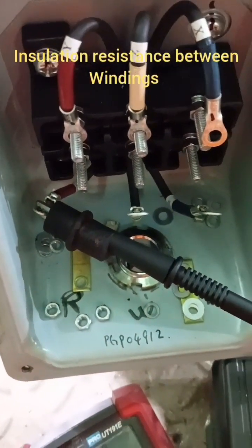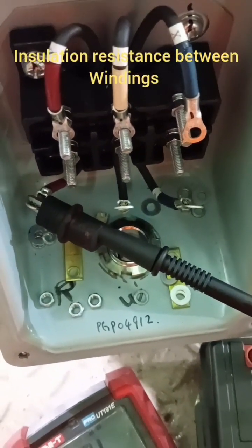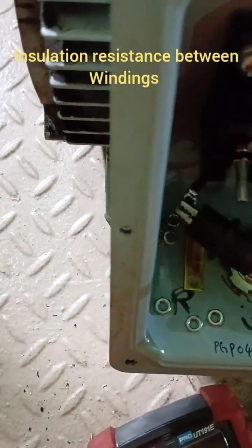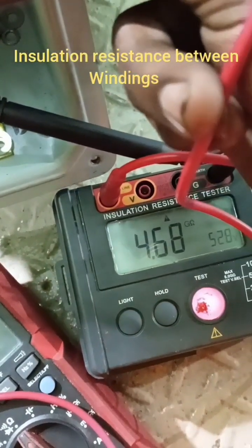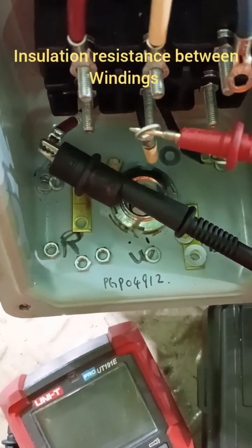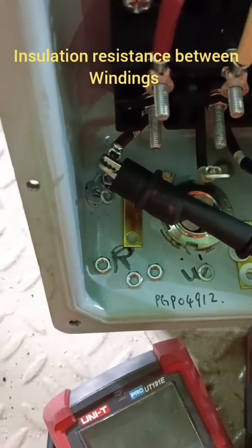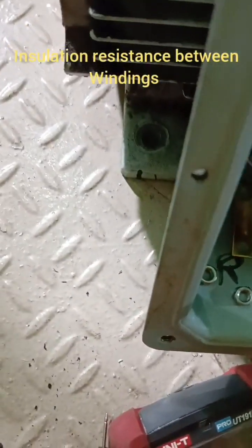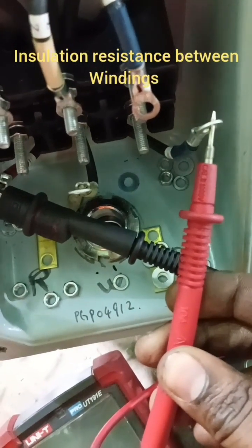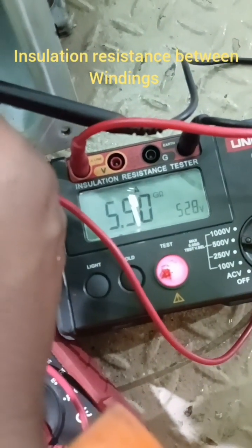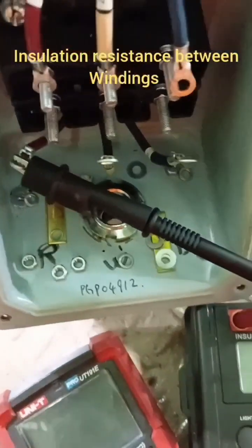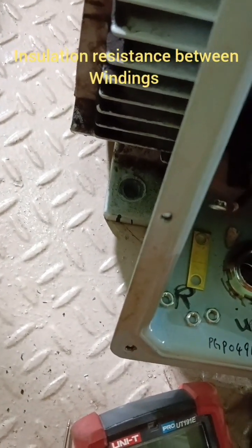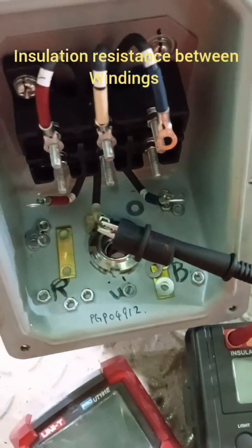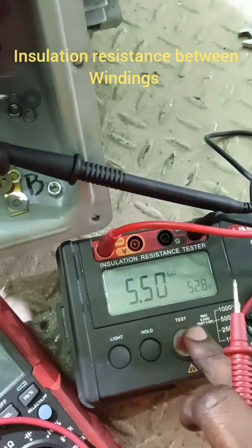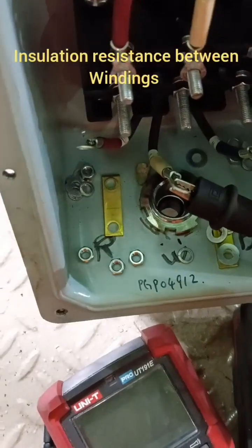Now we will measure the resistance between the windings, so we will come to know that the windings are not shorted between them. I am going to measure the insulation resistance between them. I connected the negative terminal of the Megger to one of the windings and measured between the other two windings. So I came to know these windings are not shorted. Each winding is giving almost around 5.5 gigaohms.